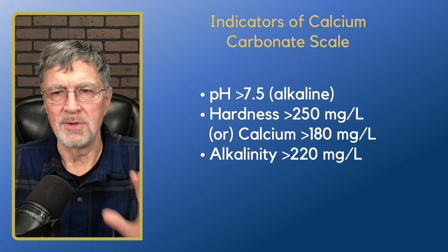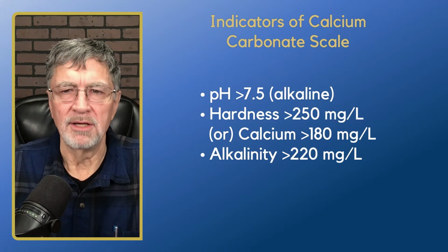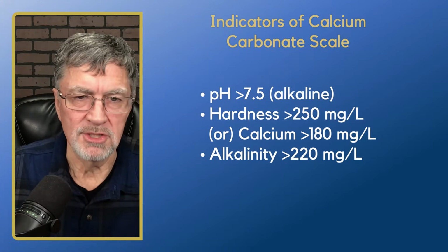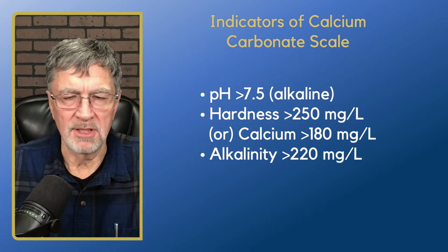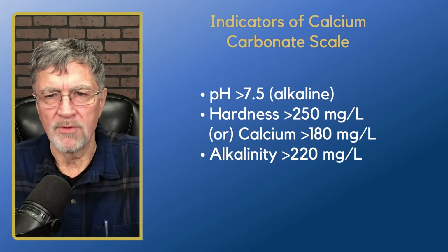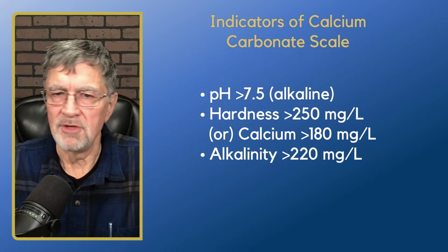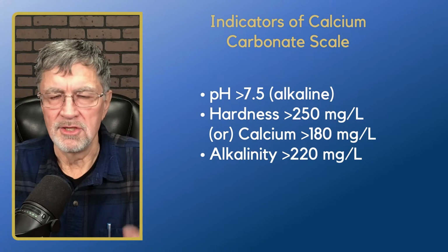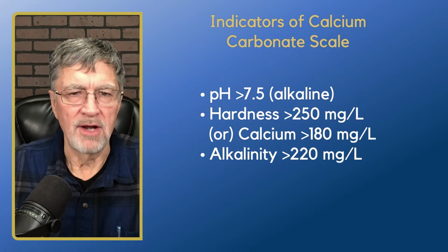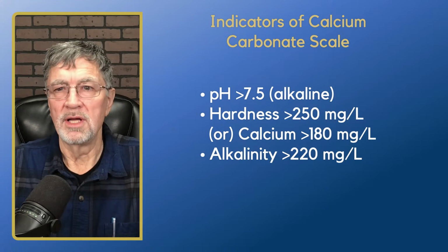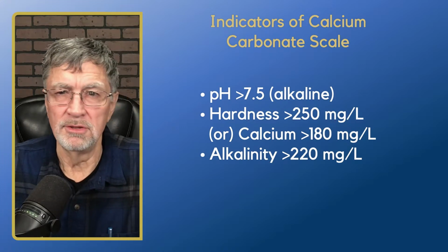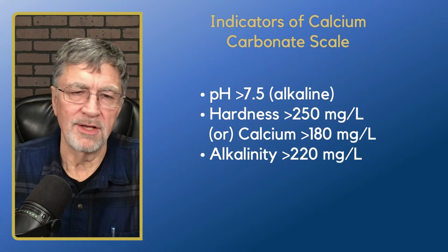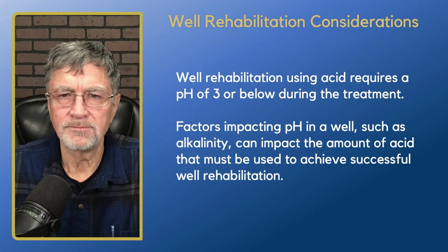This indicates that you have scaling going on in your well, or you have optimal conditions for scaling going on in your well. The LSI will help tell you that too, but these three parameters together, if you don't have an LSI, you should be monitoring these, and if you have these conditions, that'll tell you we have a strong likelihood we have calcium carbonate scaling going on in our well.